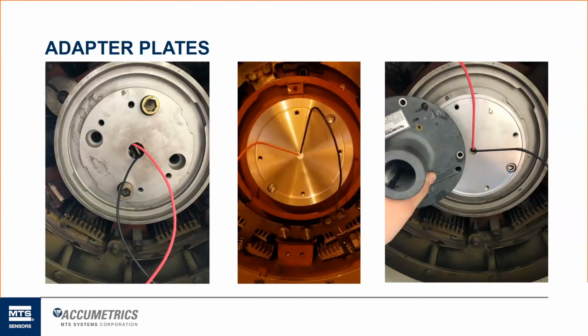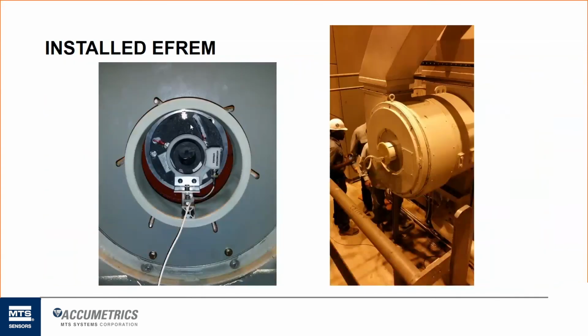And then once that aluminum adapter plate is installed, we can mount our rotor mounted transmitter, which is this gray piece, picks up this 4-bolt pattern right to the adapter plate. Once the transmitter is successfully mounted and we connect the negative and positive side of the field and rotor ground, we then can install the stationary components, which are this G10 fiberglass tube piece, which we call the top hat assembly. Over to the right, you can probably see why we call it that. That has some T80 material that allows the stationary pickup to be adjustable axially, so we can slide this pickup in and out and align it to where we see fit.